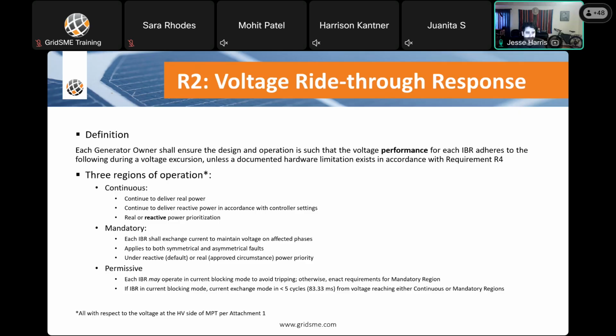But essentially, you have a continuous region where this is the region of normal operation where you continue to deliver real and reactive power. And then you have a real or reactive power prioritization. Usually this is reactive power. Once you exceed a voltage threshold, this could be low voltage or high voltage, you can enter the mandatory region, which each IBR shall exchange current to maintain voltage on affected phases. That effect could be either symmetrical or asymmetrical faults, and again, under reactive or real power priority.